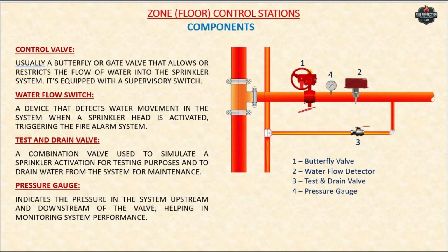Now, in the case of maintenance, suppose any maintenance or repairs are needed, the zone control valve can be manually closed using the isolation valve component. So this allows the technician to isolate the water supply to a specific zone. Some zones they can isolate, and still other zones they can keep running, without shutting down the entire sprinkler system of the building.